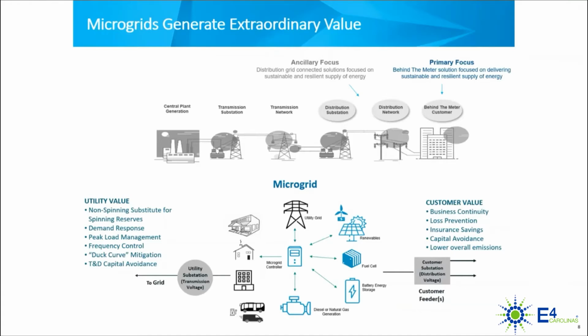All of that sits around a microgrid controller, which decides which assets to utilize and when, in order to be most efficient and effective and provide the best cost value to the customer based on conditions at that point in time. The controller makes real-time decisions on whether to use solar energy to fill battery storage or discharge it, and when it's best to run the natural gas or diesel-based generation system based on needs and what's going on with the other microgrid components.